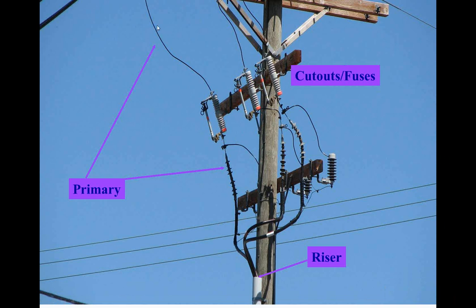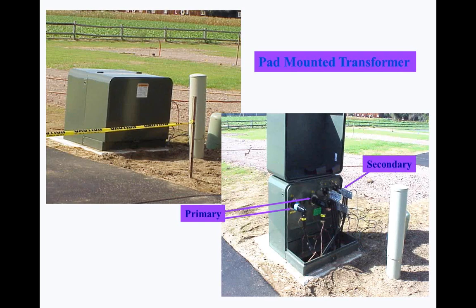So here's the typical flow. It comes down from the primary, taps, goes over this side, comes through the fuse, comes out here. And in this case, I'm feeding three-phase primary down a riser to probably an industrial customer that needs three-phase primary. So the other way you might see primary is on the ground. And if you look around, we've got a lot of underground stuff. This is a metal box. This metal box is not bolted to that pad right there. If you back into it, you hit it with your snow plow or you hit it with something, it's going to slide. It's going to move.